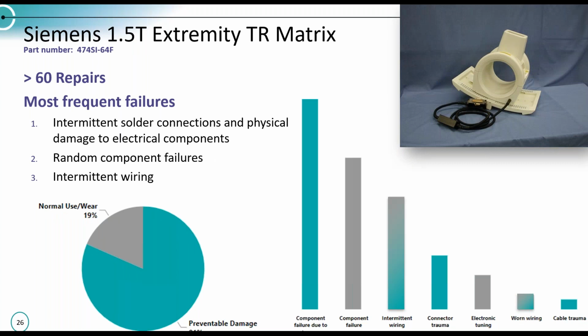And the same thing is true. I think this is our last coil that we're going to go through on our top 10, but still over 60 repairs in the last 18 months or so on this. We're coming up with a lot of intermittent solder connections and physical damage to electrical components inside of the coil itself. With this design, there are a fair amount of just component failures that occur randomly. It could be different analog components just drifting out of tune. And then intermittent wiring.